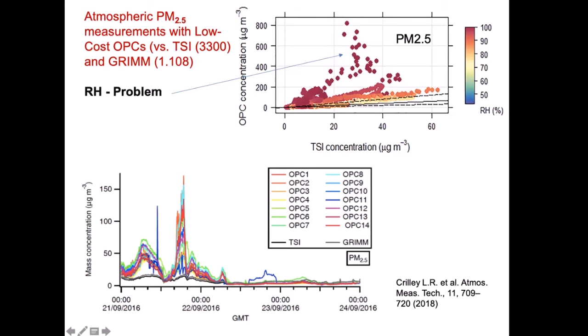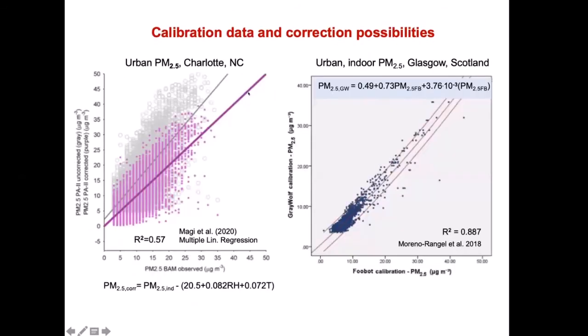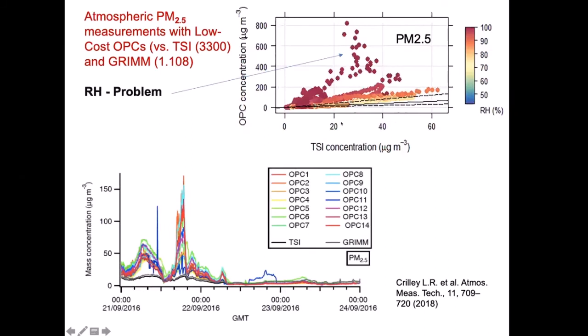At that moment where the humidity goes up, this is the data from various low-cost instruments. You see we have a situation where the concentration indicated can be 10 times the actual concentration. Similar situations are published in 2018 by Crilley et al. in Atmospheric Measurement Technology. You have here 14 various optical particle counters, and this bottom dark line is measurement by a research grade instrument, and everything else is PM2.5 measurement by low-cost sensors.